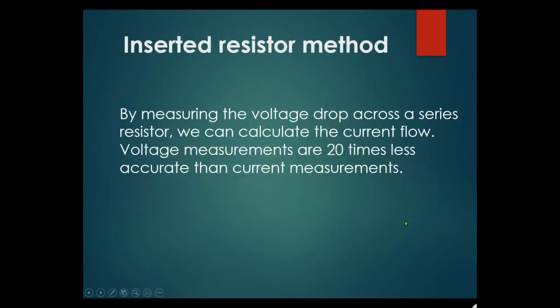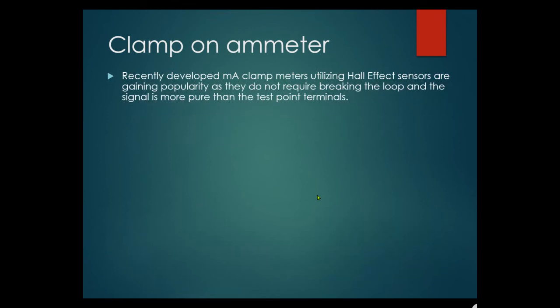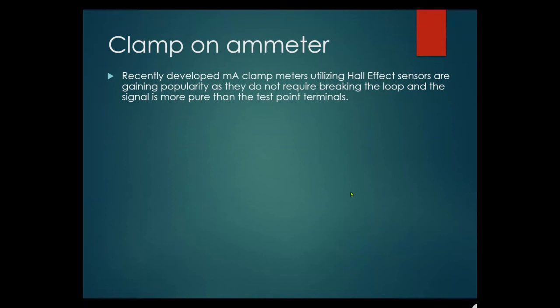By measuring the voltage drop across a series resistor, you can calculate current flow, but voltage measurements are 20 times less accurate than current measurements. A newer tool is the milliamp clamp-on ammeter utilizing the Hall effect — gaining popularity because it does not require breaking the loop and gives a more pure signal than test point terminals. Previously, sharp terminals were used to pierce wire insulation to test voltage drops, but that damages the insulation.